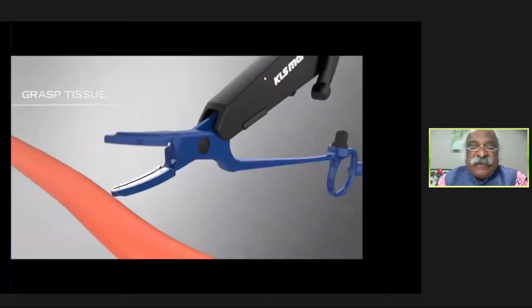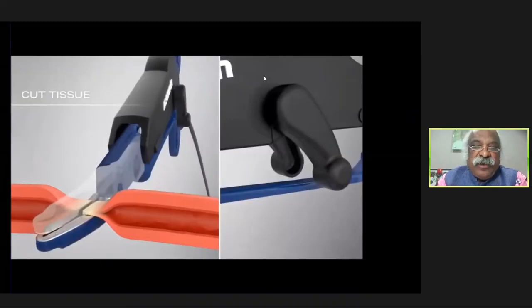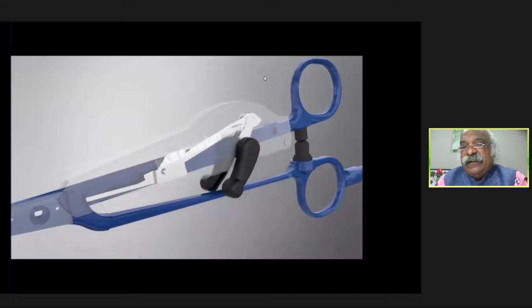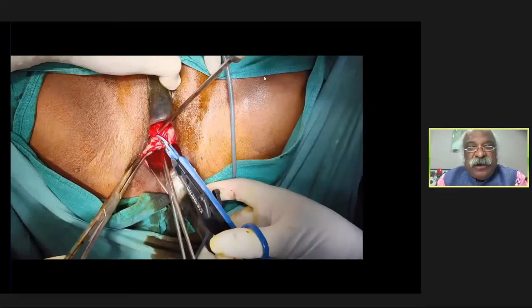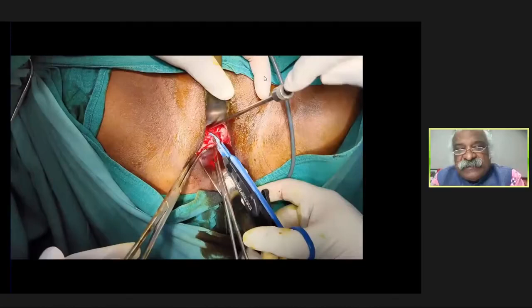I've used the Martin IQ cut, where the sealing and coagulation are done in the same sitting, whereas on the other side I have used the Mark clamp conventionally. The advantage, this side I've used the IQ. You can see the coagulation, and on tracing, the cutting will be there. Coagulation is very good. The only limitation is that the electrode length is very small. I have suggested that this length is not feasible. It's not very good for vaginal hysterectomy. You should increase the length so that we can do more and better.